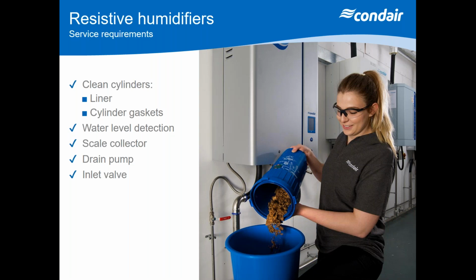Again, very important to look at drain pumps and look at the inlet valve to make sure that is actually operating correctly. Always worth just taking the strainer out in front of the valve to make sure that's clean, so you're getting the correct flow rates through. Because if you don't, then you get inconsistent levels on your floats, and you won't get the correct operation out of the unit. So that's now the 2 electric steam humidifiers you see in the marketplace.